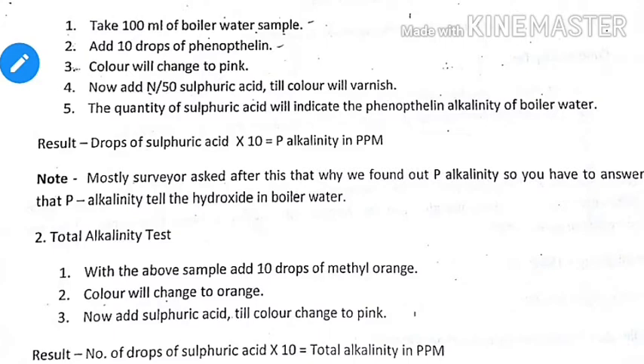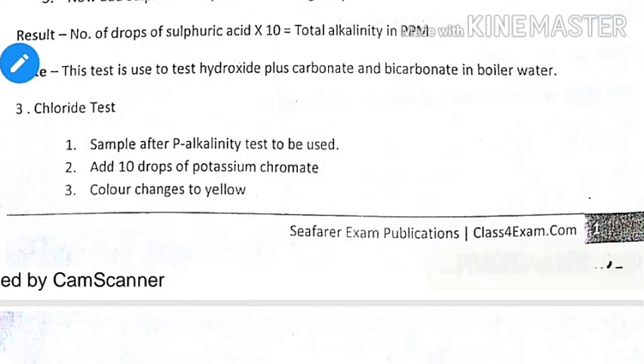Add alkalinity chemical into the boiler water or condensate water to increase the alkalinity. Chloride can enter the boiler water through condenser leakage or fresh water generator/evaporator leakage. This chloride can form acid, which can degrade or erode the tubes. A base should be present in the boiler water to prevent acid corrosion, so we add a basic compound or alkalinity chemical.